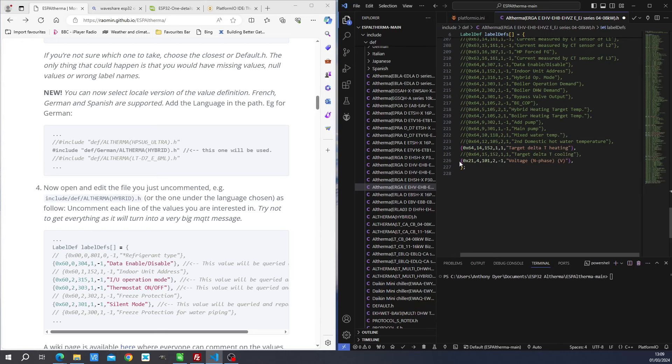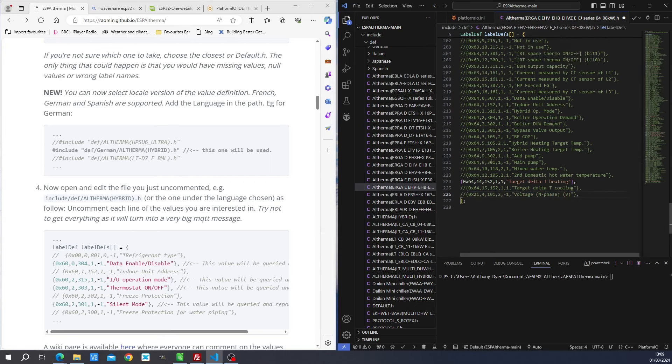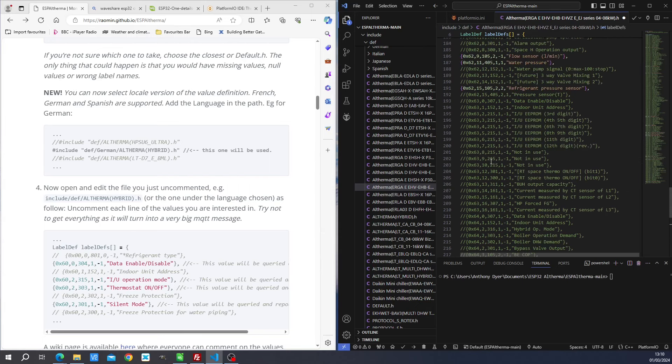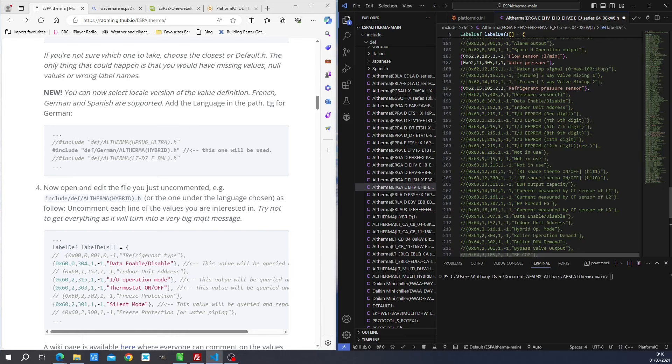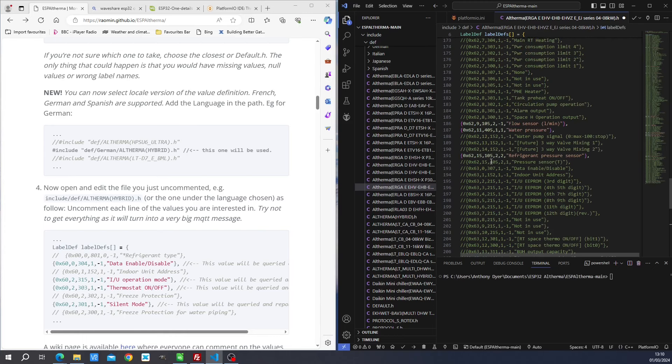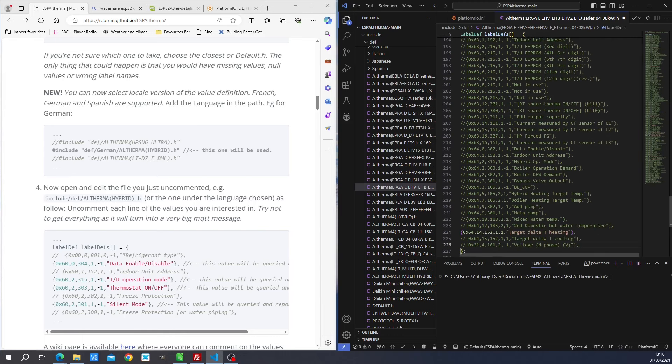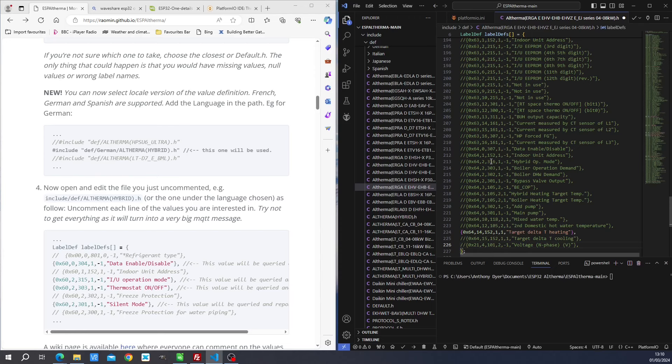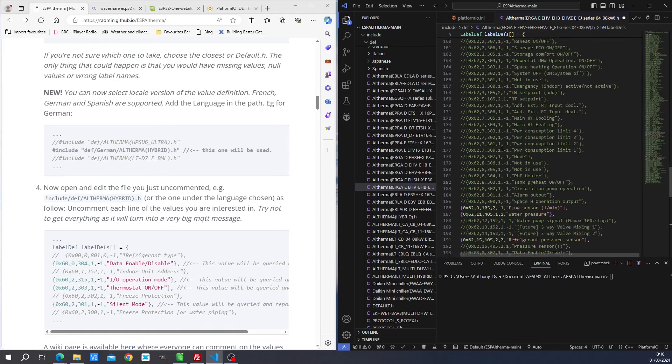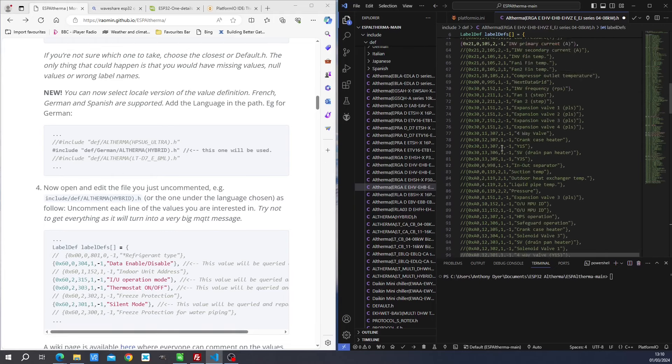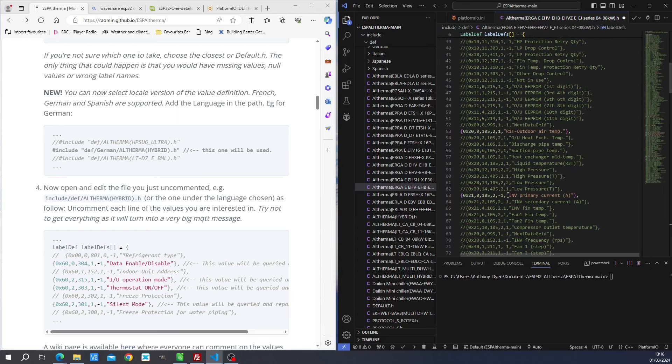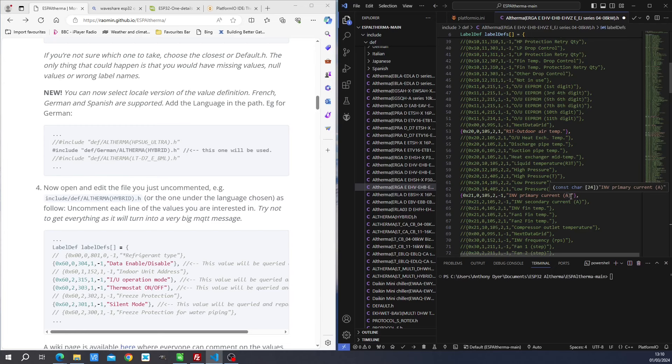This is the voltage for the inverter on the other side of the compressor. So this is not giving you supply voltage. And we're going to talk about the fact that there is no data here for actual real power supply. And that is a bit of a challenge shall we say because we don't have information on the supply voltage from this. And we do not have any information about the power factor for the heat pump. But we have other ways of getting that information. The other thing I want to just mention is that the primary current here is only the current going to the inverter. It is not the current which is used by the hydrobox for ancillary operations such as being on standby and running the pump. We'll talk about that in a bit more detail later on.